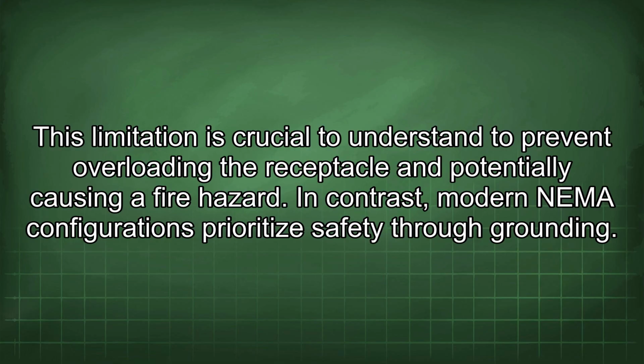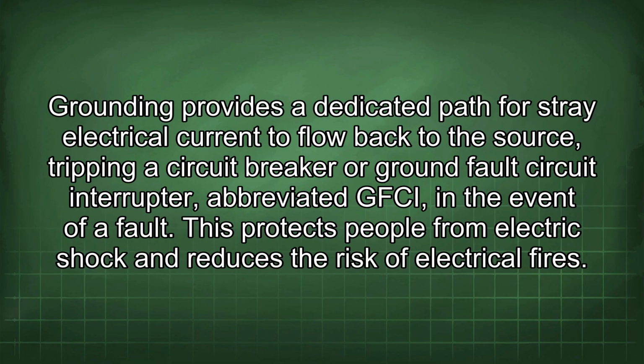In contrast, modern NEMA configurations prioritize safety through grounding. Grounding provides a dedicated path for stray electrical current to flow back to the source, tripping a circuit breaker or ground fault circuit interrupter, abbreviated GFCI, in the event of a fault. This protects people from electric shock and reduces the risk of electrical fires.